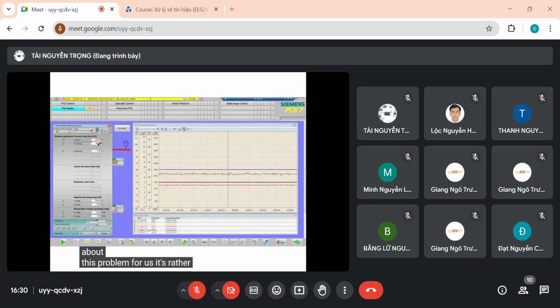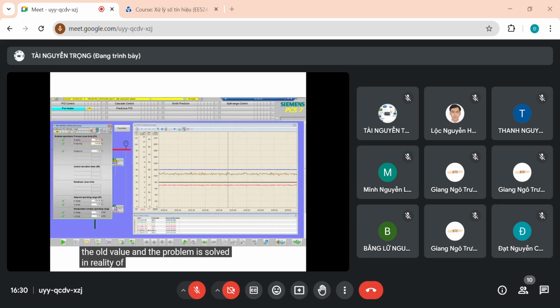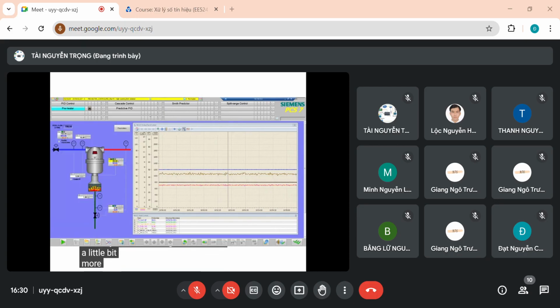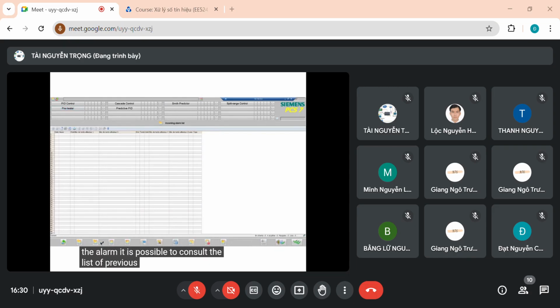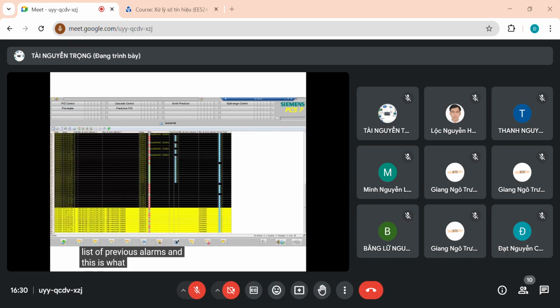For us, it's rather easy. We put the old value and the problem is solved. In reality, of course, things will become a little bit more difficult, and then you can quit the alarm. It is possible to consult the list of previous alarms, and this is what you obtain. Of course, here there is only one type of alarm, but you can see that this high warning limit violation has occurred several times. The last time that it occurred, it was active for 35 seconds, and it was quitted after 43 seconds.